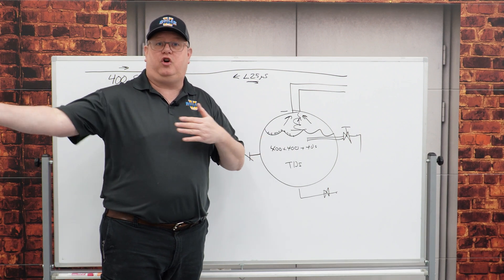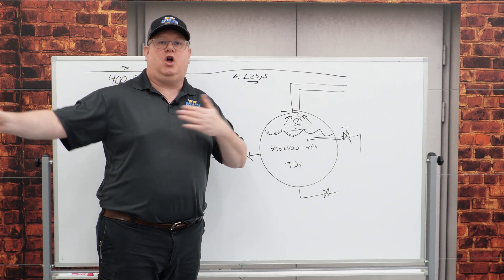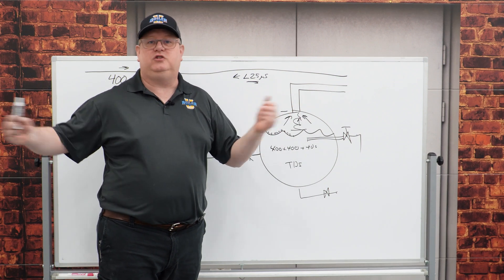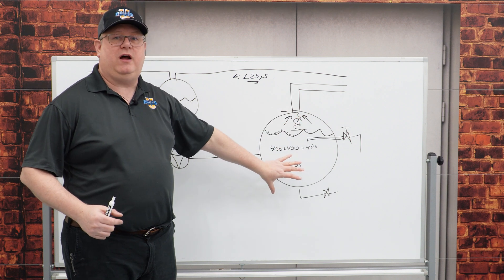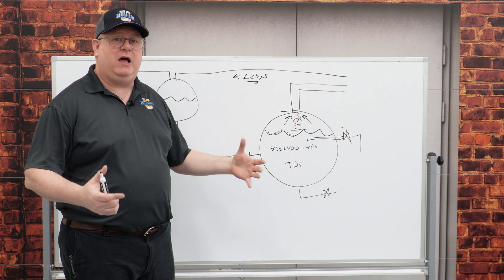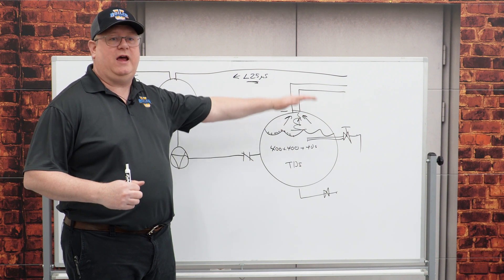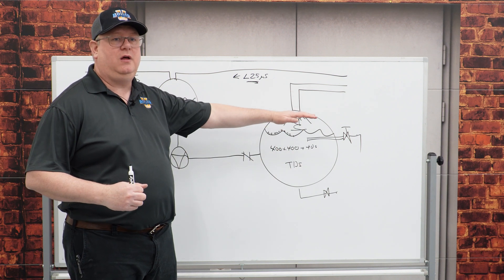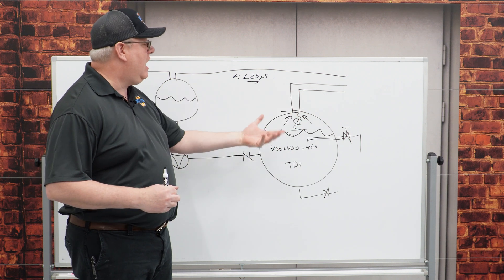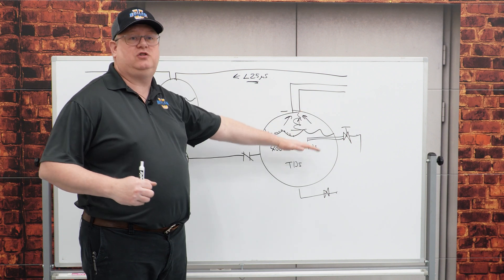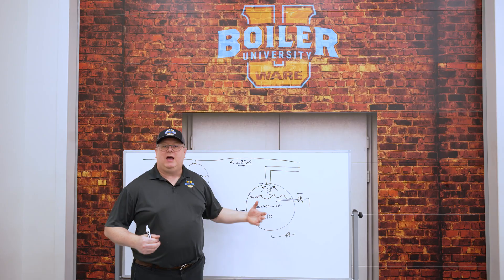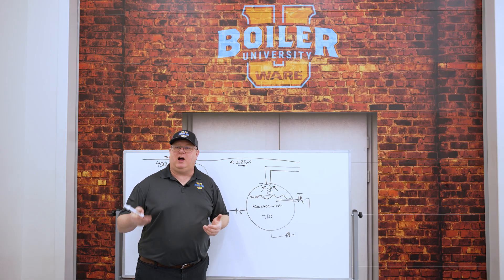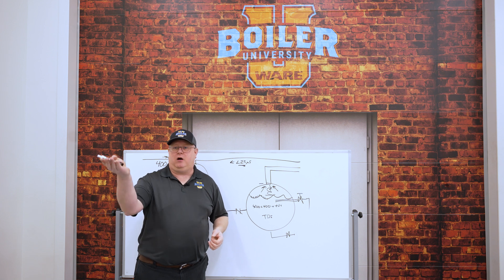It's going to be a short-term loss of energy when we skim or blow down aggressively, but ultimately we need the boiler to stay online. It's not unusual to get extreme fluctuations in your water level and have low water trips if conductivity goes beyond our limits.